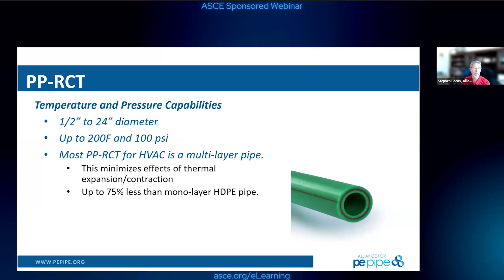So the inner and outer layer are PPRCT, but the middle layer is actually a glass fiber reinforced layer. That glass fiber layer's main purpose is not to add more hoop strength or pressure rating capability—it's really to minimize the thermal expansion and contraction of the pipe. It gives about 1/10 the amount of thermal expansion/contraction you might see in a non-reinforced polypropylene pipe. That really helps when designing mechanical systems inside large data centers, so you don't get those large temperature movements. You can compensate for that, but this material means you don't have to.